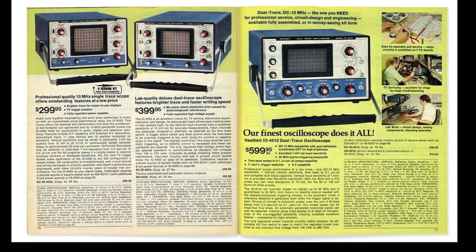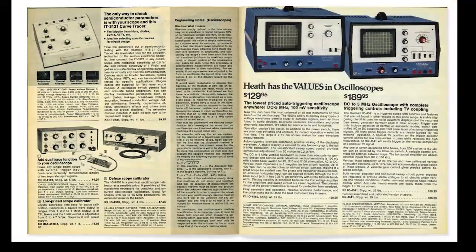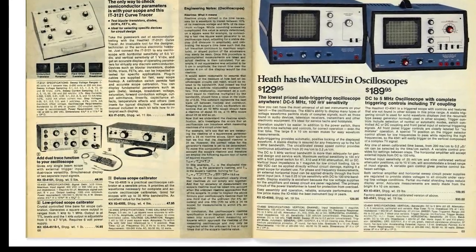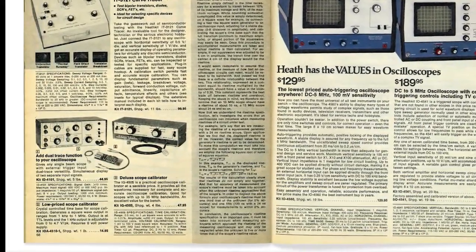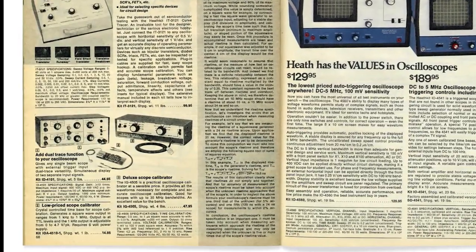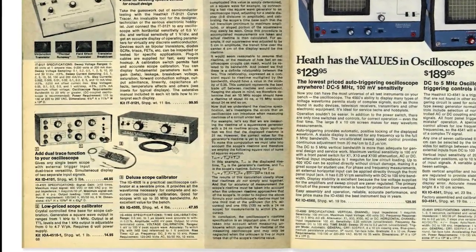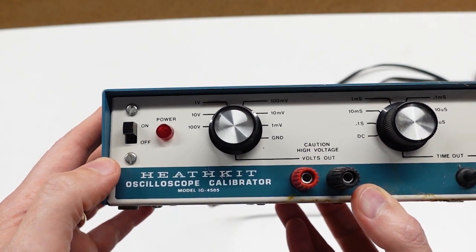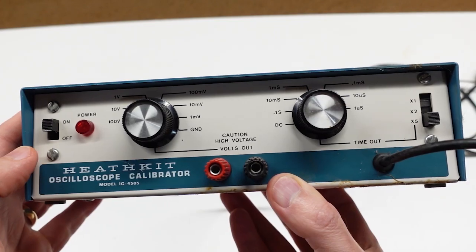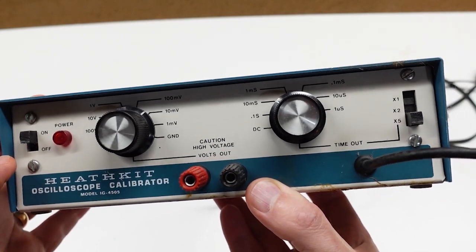An oscilloscope calibrator like this IG4505 is a bit of a limited utility test instrument. Its name accurately describes its intended function, but digging a bit deeper, you quickly see that it's essentially just a simple function generator. And by simple, I don't mean it's primitive, but rather I mean its range of functionality is pretty simple. Let's take a look at the specs to see what I mean.